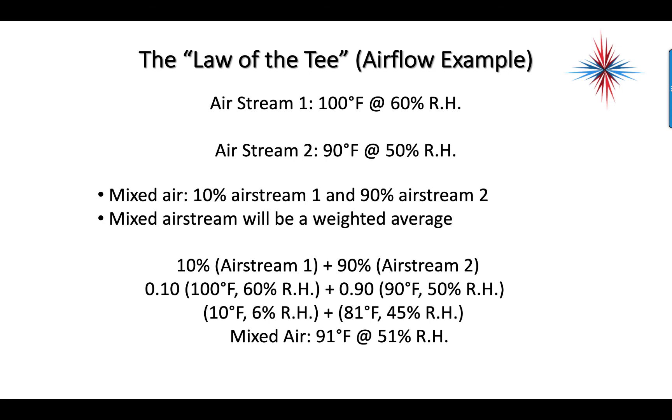So multiply the 100 times 0.1 and the 60 times 0.1 - again, 10% equals 0.1 - and we come up with 10 degrees at 6%. We take 0.9 times 90, we get 81. We take 0.9 times 50, we get 45. Now we add those two together - we have our mixed air at 91 degrees Fahrenheit and 51% relative humidity. Try it on your own examples and see what comes up.